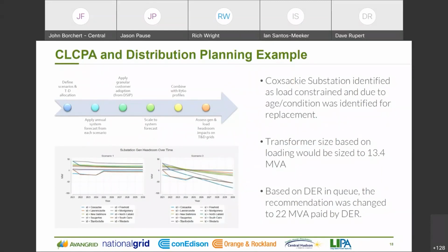The area load required a new transformer to be installed, which would have been 13.4 MVA. While this was adequate for the expected load and future load, and for the firm DER that was interconnected or to be interconnected in the area, the area had a large amount of DER in queue.